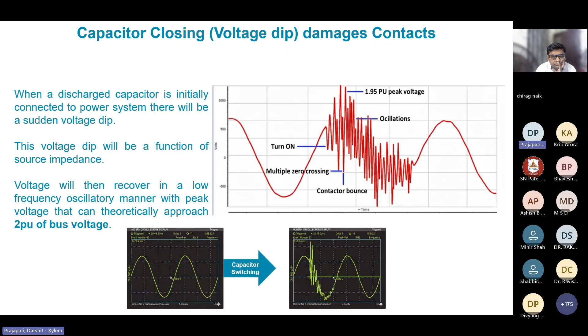Depending on the size of the capacitor and the system impedance, large capacitor banks result in low frequency ringing, while small banks result in higher frequency ringing or transients. The initial peak of the voltage can have a magnitude of up to 2 per unit in the system.